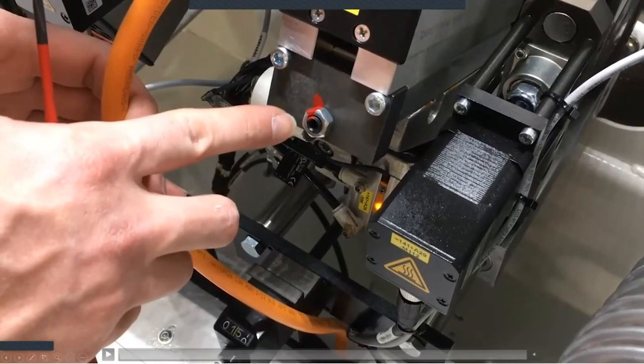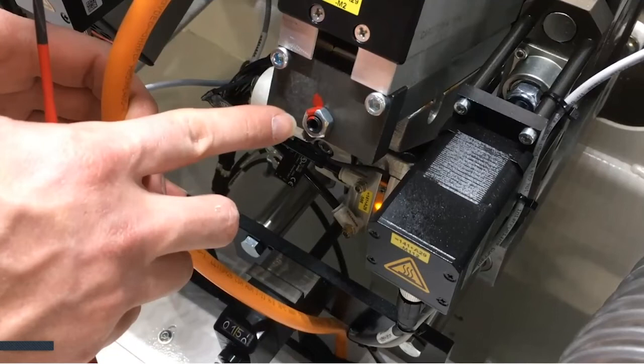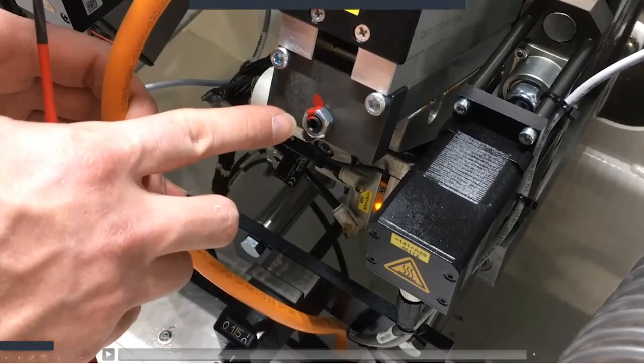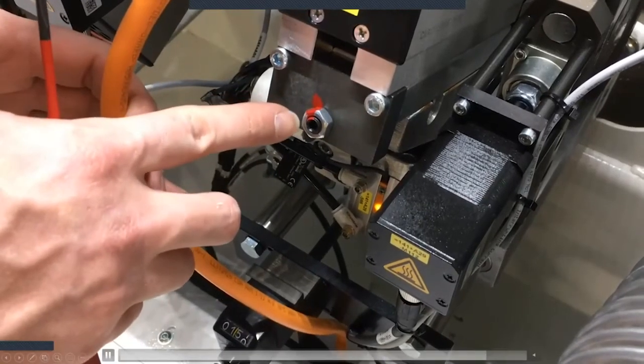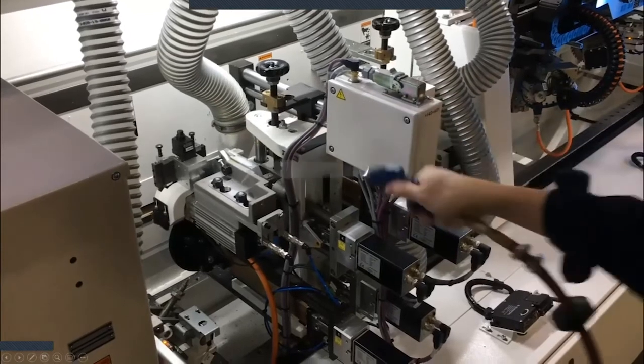Anytime I see something marked in red, especially from the factory, our technicians will mark using techniques such as this. Anytime I see this, I do not want to touch this adjustment. That's telling me that this is set where it needs to be set. I do not want to move it, otherwise I risk my station being out of adjustment and issues down the road.